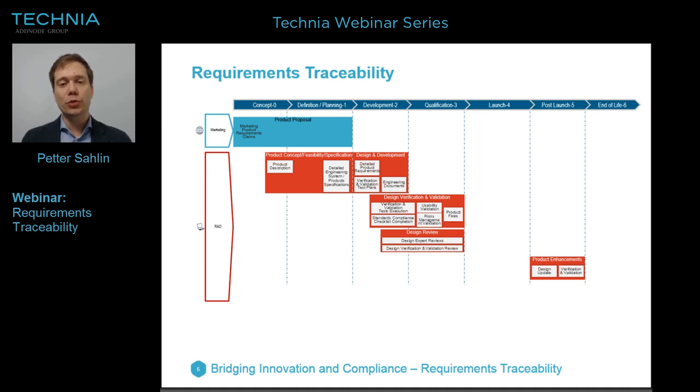In that part, we come back to the usability validation. We come back to the risk definition and the risk mitigations. And we want to make sure that those are met with relevant validation. If, at a late stage, we perform fixes and corrections, we want to make sure that we can support this with proper regression testing, and with that we want proper support.